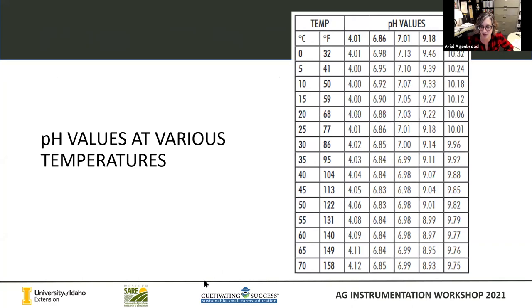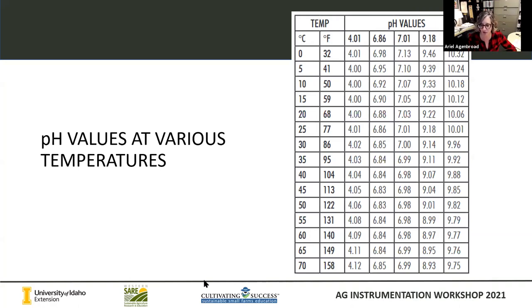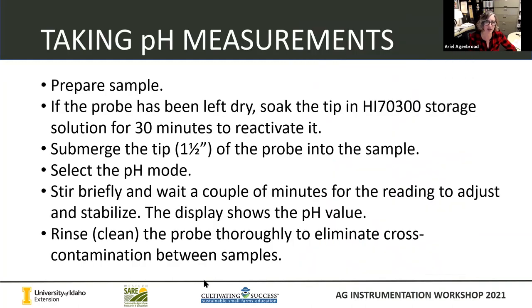This chart shows you: if your solution temperature is say 77 degrees Fahrenheit and you are using the 7.01 solution, you should actually be calibrating to 7.01 — you're in the right spot at that temperature. At any other temperature you're going to adjust slightly up or down to compensate. This chart is also in the manual and in the materials that came with your probe. Once we get that done we're off and rolling, and with this new model, once it's calibrated, you may not have to calibrate it again for a while.